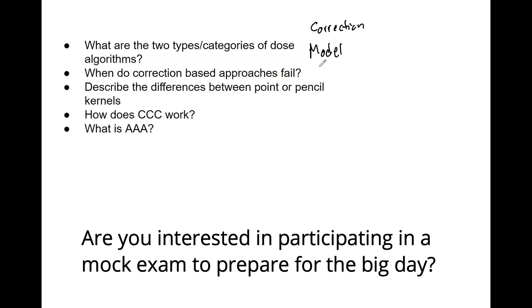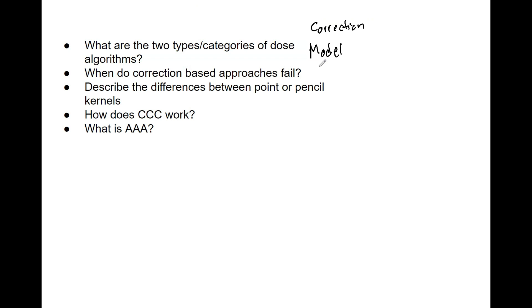Whereas model-based are much better in small fields and more complex heterogeneities. So describe the difference between point and pencil kernels. We'll start with point kernels—these are a point-by-point dose result from Monte Carlo for each site.